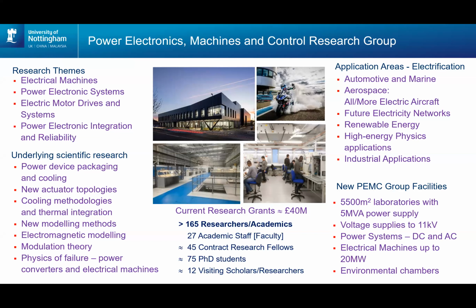And this has given us 5,500 square meters of laboratory space, including some very large labs where we can work at high powers. And indeed, we've got a 5 MVA connection to the, well, it was Western Power Distribution Network. It's now National Grid Distribution Network. And then we can work within that building at power levels up to about 20 megawatts. Because when you're testing electrical machines, you're only feeding the losses into those systems. Voltages up to 6 kV DC and 11 kV AC. So we've got a big facility.